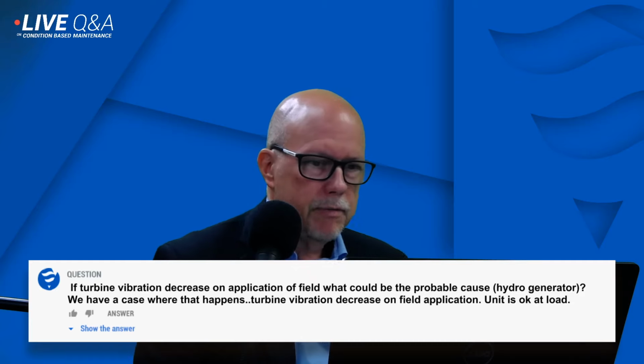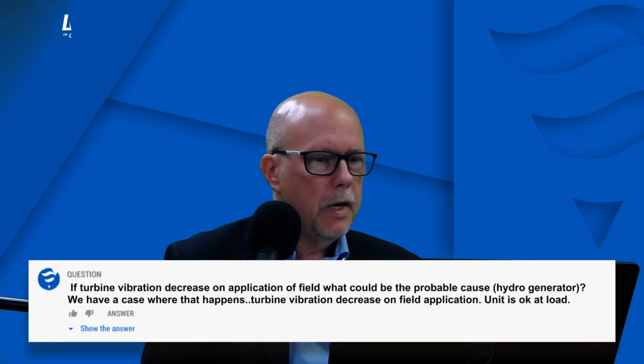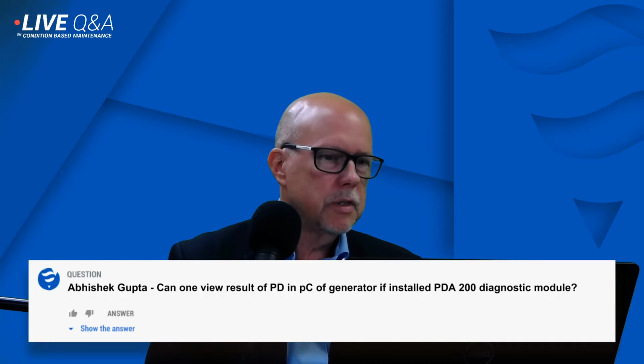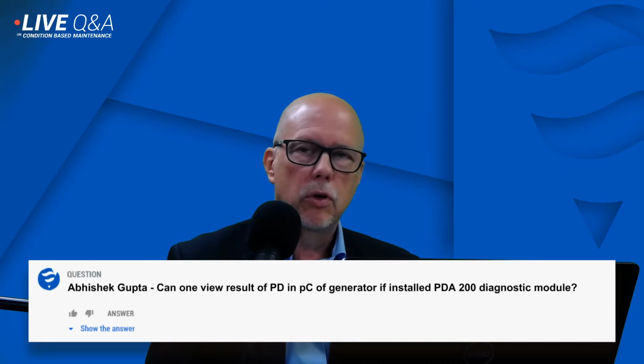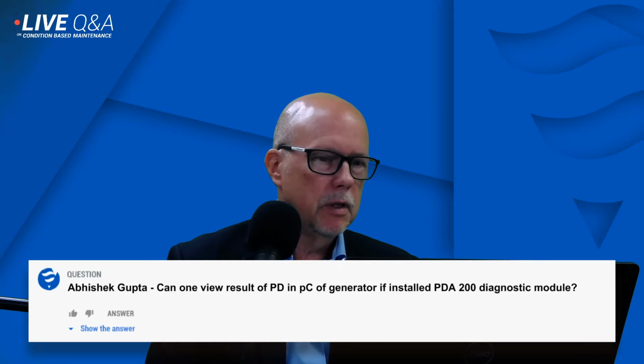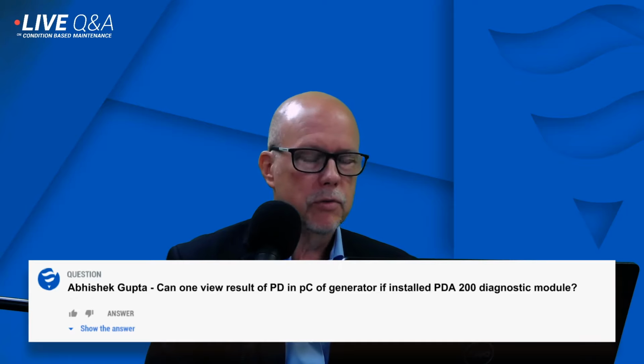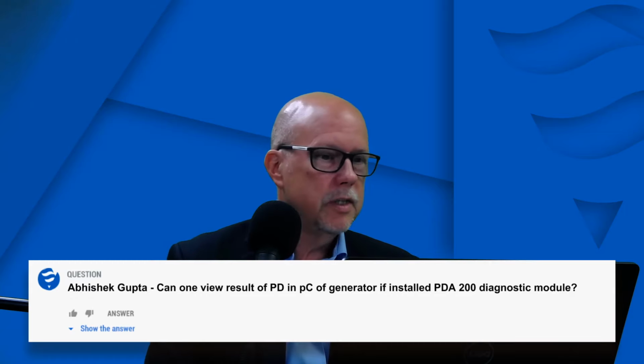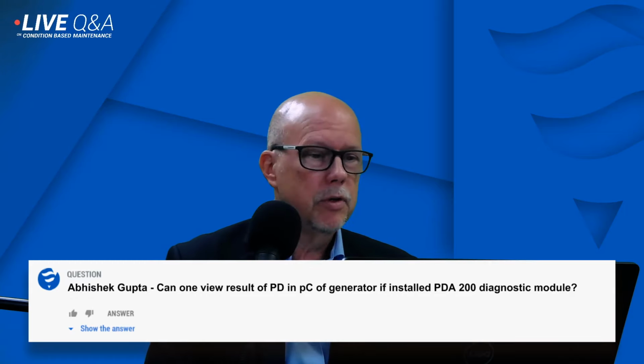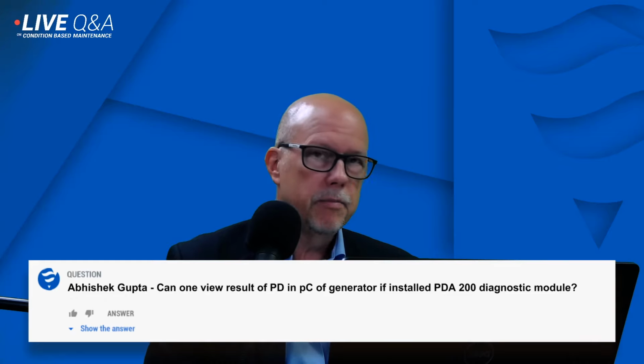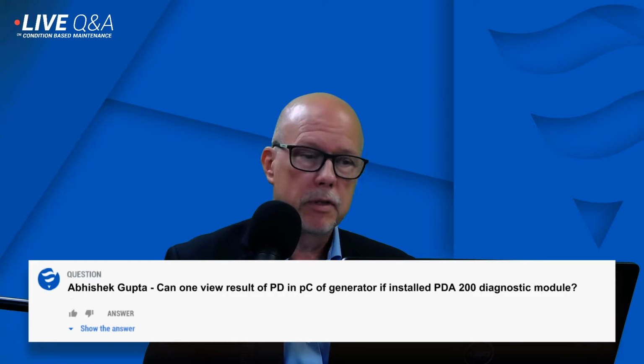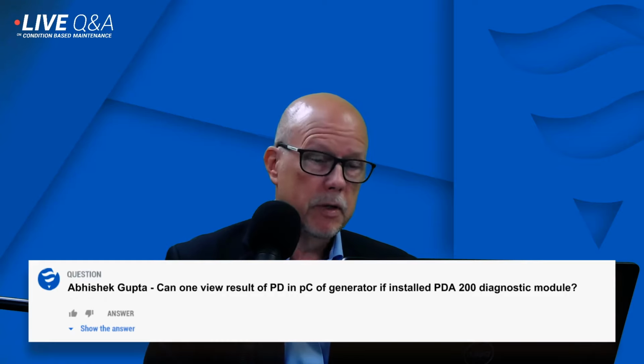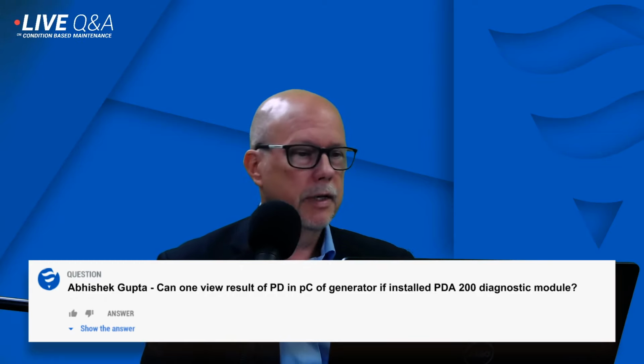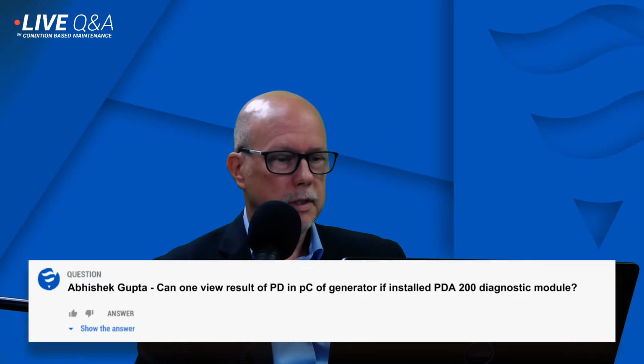And we also had a question from Mr. Gupta. And the question was, can one view results of PD in picocoulombs of generator if installed the PDA 200 diagnostic module that we provide? And the answer, quite simply, to that is no. The PDA 200 does not measure in current, it measures in voltage. So it will be able to display the quantity of pulses, the general location of the pulses, and the intensity in millivolts. It does not display or measure PD data in picocoulombs.